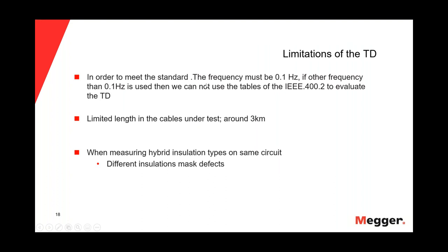Regarding the limitations of Tan Delta: in order to meet the standard, the frequency must be 0.1 Hz. If other frequencies are used other than 0.1 Hz, we cannot use the tables of the IEEE 400.2 to evaluate the Tan Delta. Another limitation is the limited cable length under test — around three kilometers. Another major factor is when measuring hybrid insulation types on the same circuit — for example, some EPR, some PILC, some XLPE. The different insulation types will mask the defects depending on what insulation types are in the circuit. And if you're not using 0.1 Hz and three steps, there is no table to compare to.